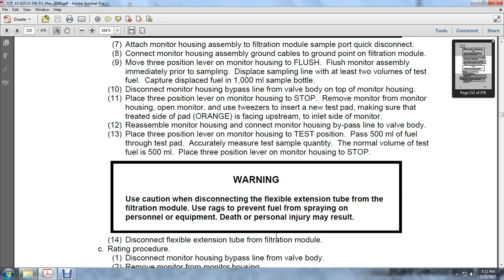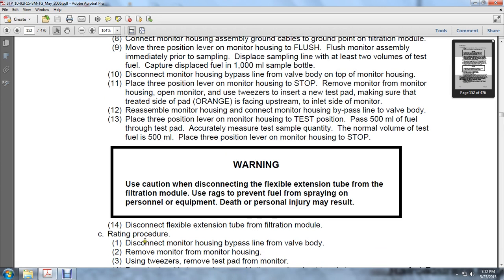Warning: when disconnecting the flexible extension tube from the filtration module, use rags to prevent the fuel from spraying on the personnel or equipment, or death or personal injury may result. 14. Disconnect the flexible extension tube from the filtration module. Disconnect the monitoring housing from the bypass line of the valve body.